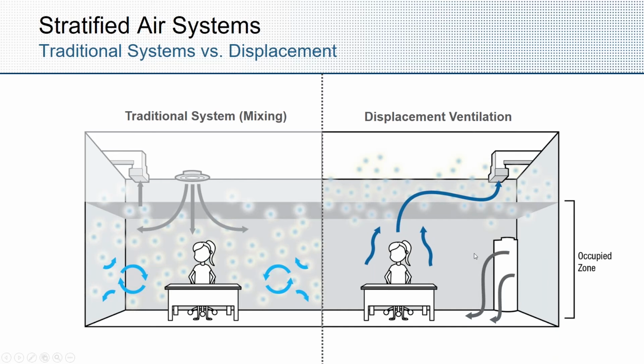In displacement, whether it's displacement or underfloor air, you're supplying from low level, either in the wall near the floor, or in the case of underfloor air, directly from the floor. The idea is you're supplying the air at a slightly elevated temperature, anywhere from 62 to 68 degrees, fairly common between the two systems. And it's a single-pass system.